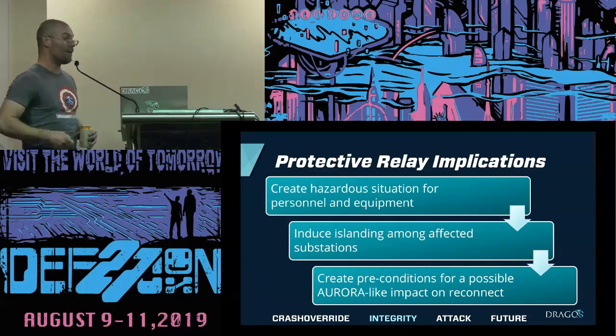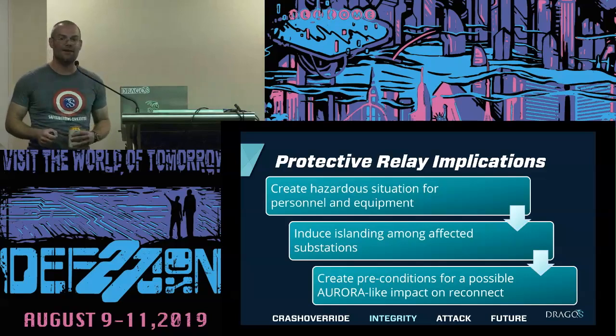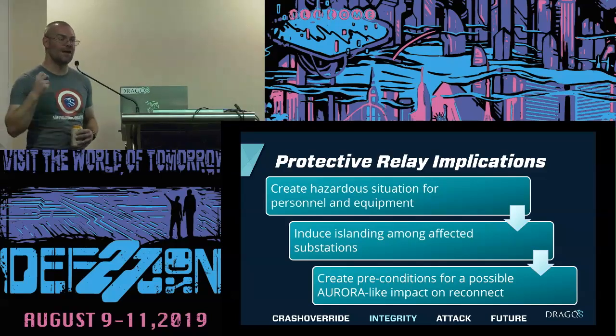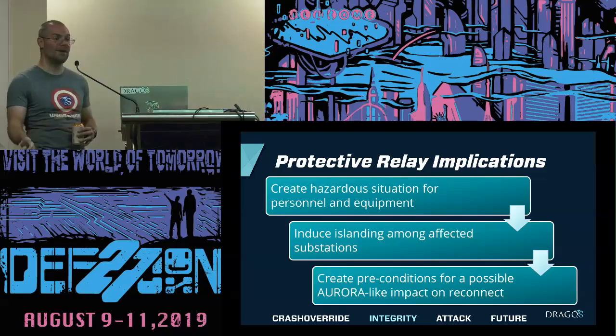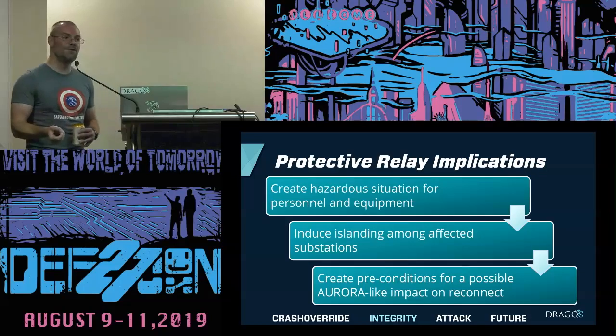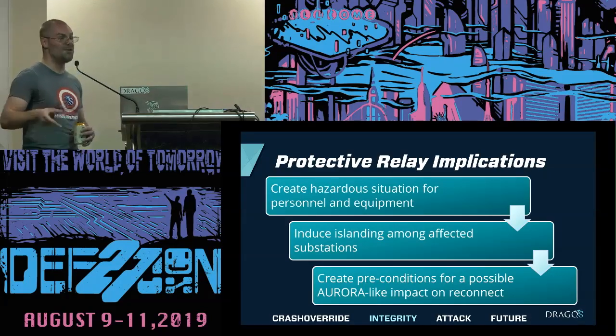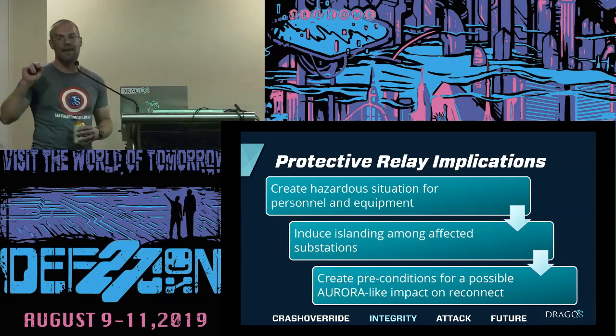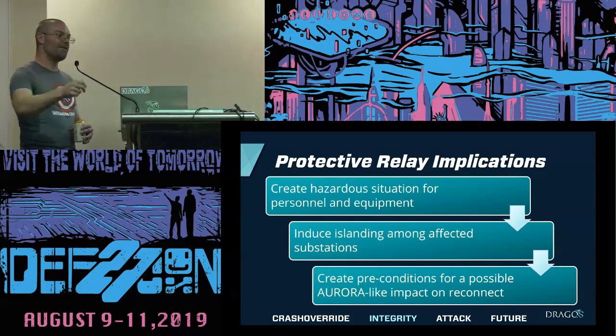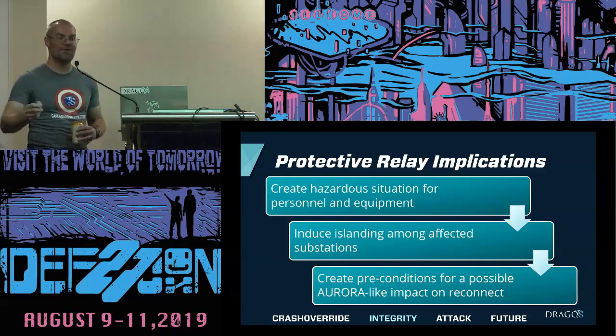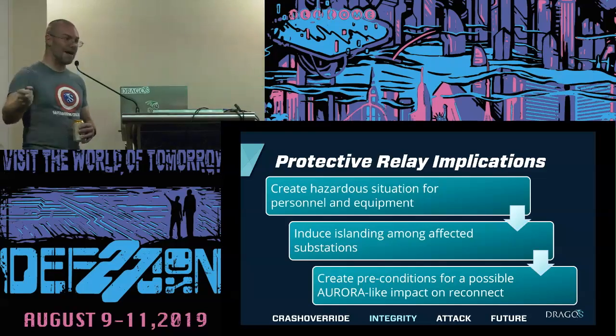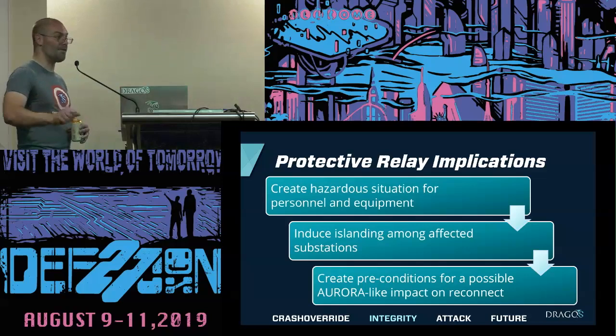Or the really scary scenario, if you start getting into protective relays at generation, is that manipulation of protective relays from a generation environment starts getting you into a spot where you can induce an aurora-like effect on generating equipment. Aurora was a manipulation in frequency relative to electric generation operations that results in a generator rocking back and forth between frequency extremes, inducing physical damage.